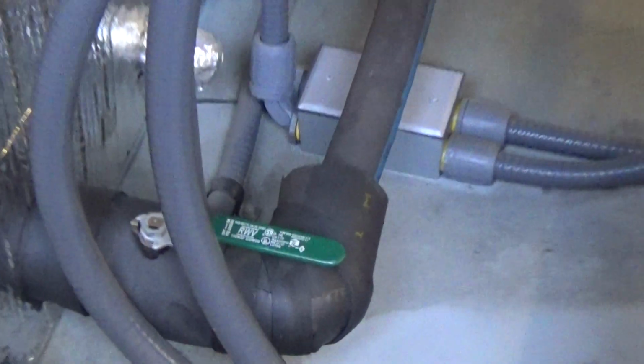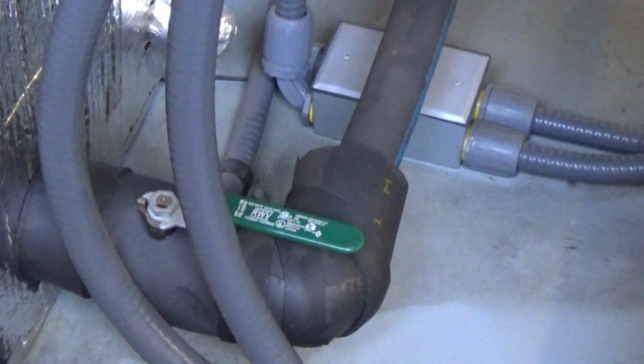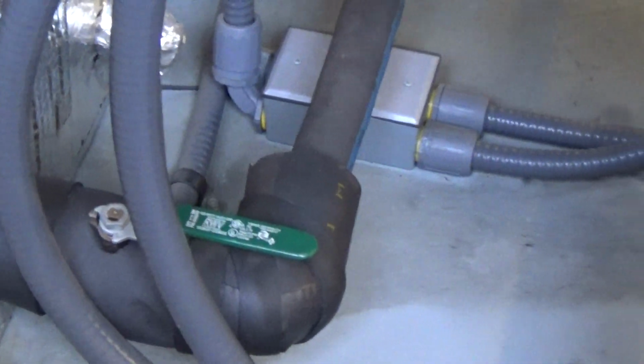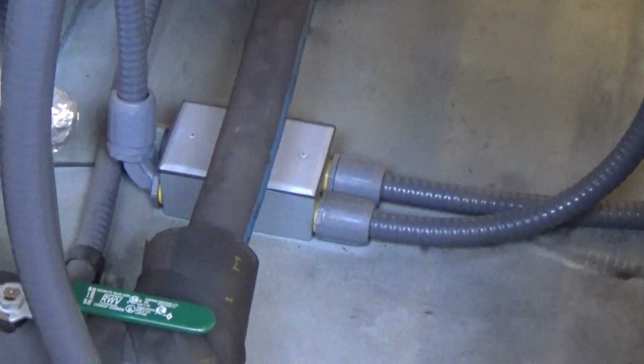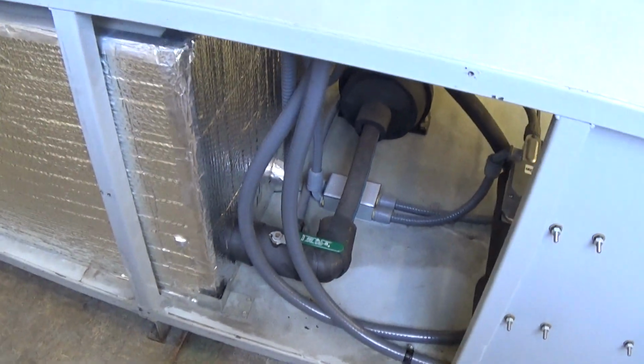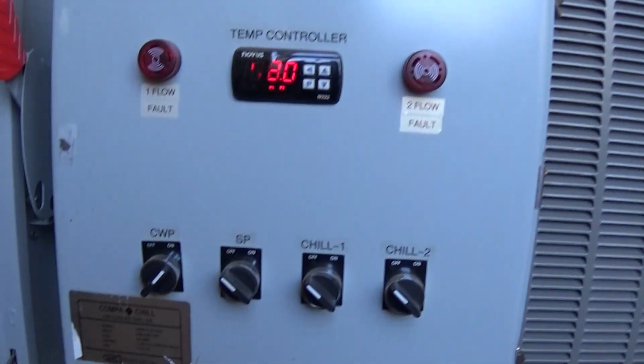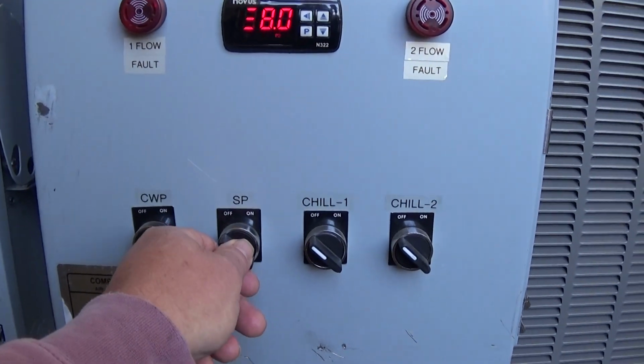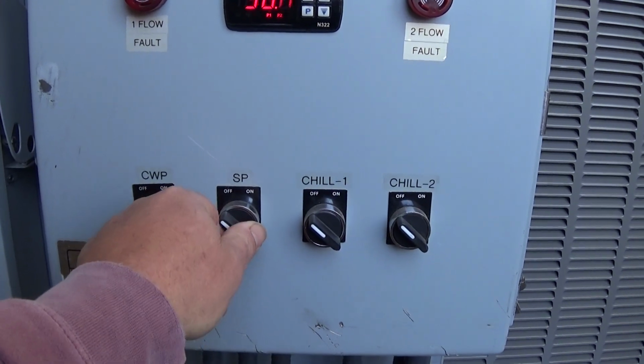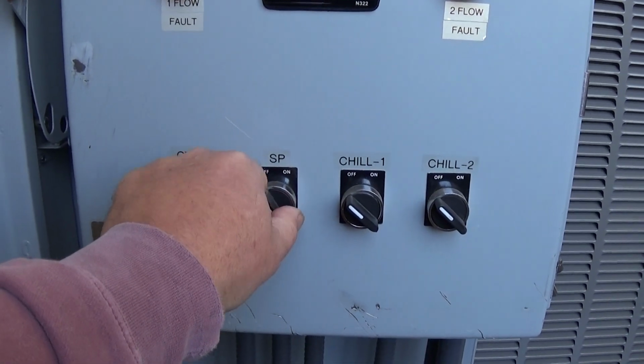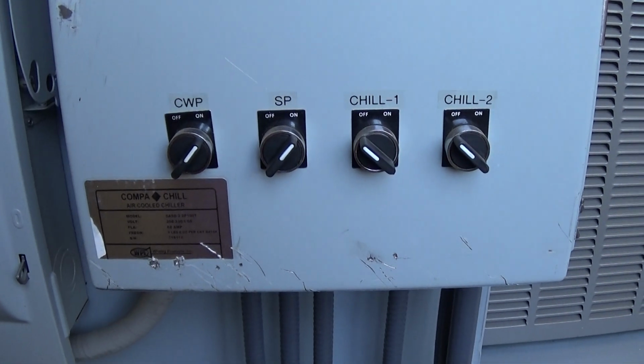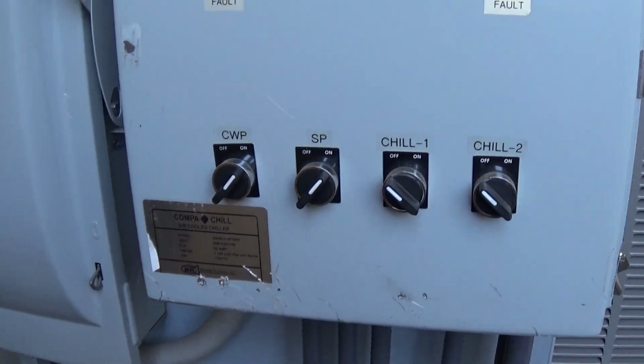That valve there, that should be left open, wide open all the time, as that goes to the suction side of the pump. You never want to restrict the flow to the suction side of the pump unless it's a service issue. Then we can turn on, you don't have to cool it, but then you turn on the supply pump for the process supply, so now we got both pumps running.